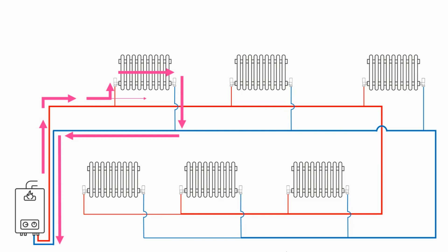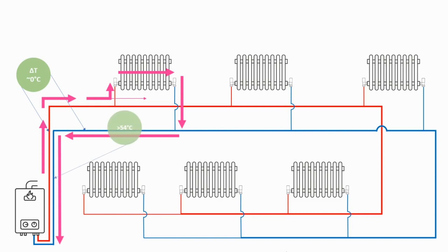Secondly, this short circuiting will allow the return temperature to increase much quicker than it would normally so you've no longer got a delta T of 20. It's highly likely that the return temperature will rise above 54 degrees which is dew point and that will mean that the boiler will no longer be in condensing mode, severely impacting boiler efficiency.